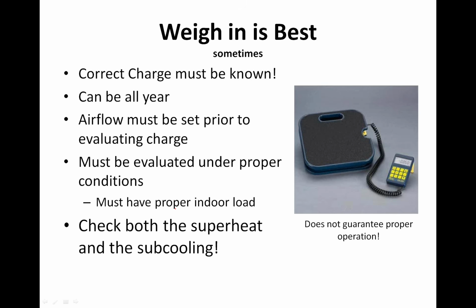Most of the time we're talking about a system that is installed in the field, and we have an unknown, which is the line set length, and maybe the evaporator coil. Maybe there are two or three different evaporators you could match up with it, but we don't know what size evaporator we've got, so we have a bunch of unknowns. The great thing with the weigh-in is that if we know how much charge is supposed to be in the system, it can be done all year.